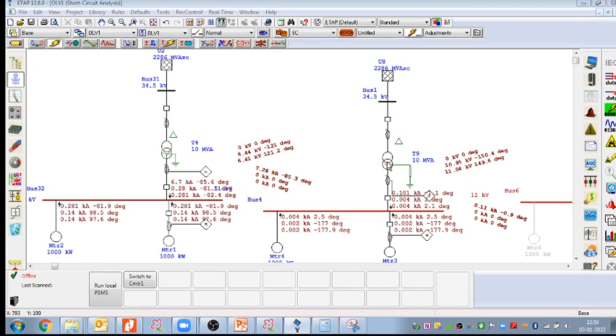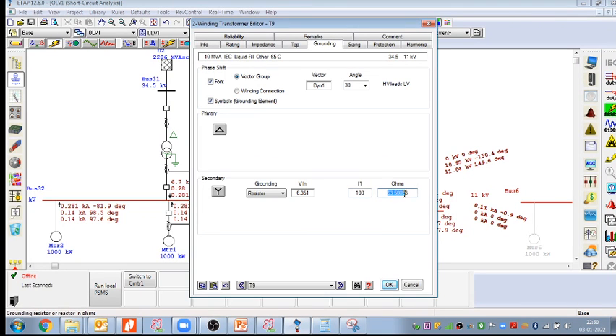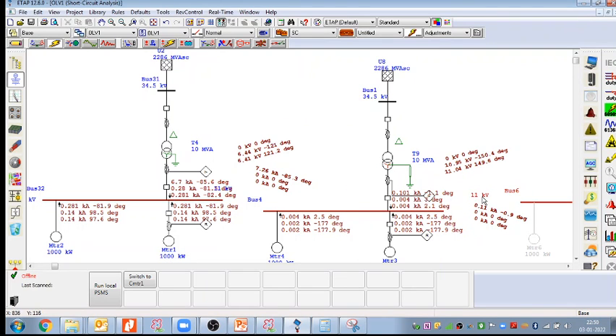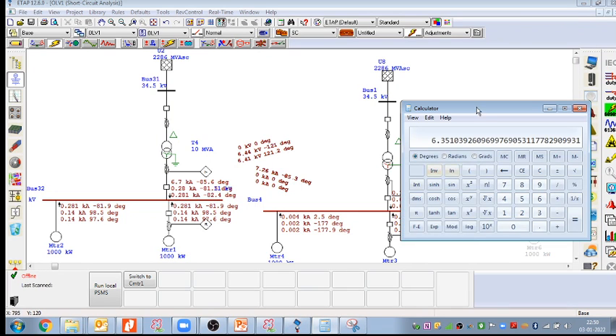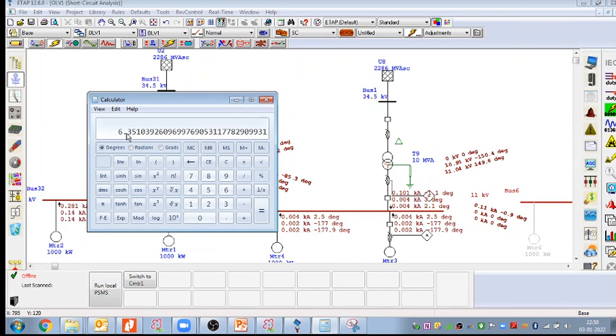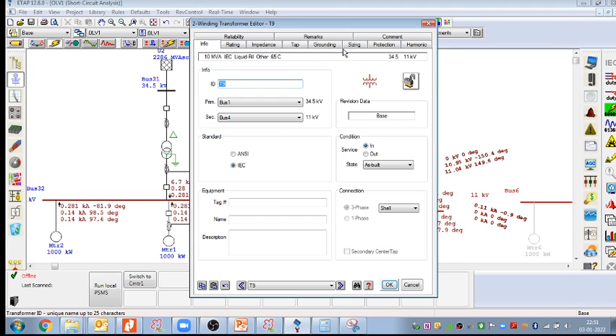In my ETAP, I have taken 63.5 ohms because my voltage is 11 kilovolts. As you can see, this is 11 kV here, 11 kV here. When I divide this 11 kV by root 3, it comes to 6.35 kV. Again I divide by 100 because I want to limit the current to 100 ampere. That gives 0.0635, multiplied by 1000 to convert kV into volts, so 63.5 ohm comes, and ETAP automatically calculates that here.